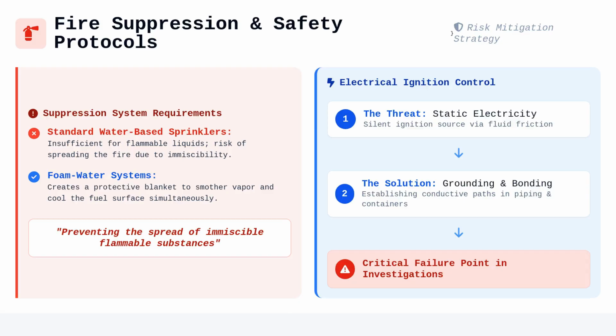We also perform a meticulous evaluation of grounding and bonding protocols for any equipment used to transfer these liquids. Static electricity is a silent and persistent ignition source. A simple spark generated by fluid friction during a transfer process can trigger a massive ignition if we have not adequately dissipated the static charge. This is why you will see specific requirements for conductive paths in piping and container management, a detail that often becomes a primary failure point during a fire investigation.